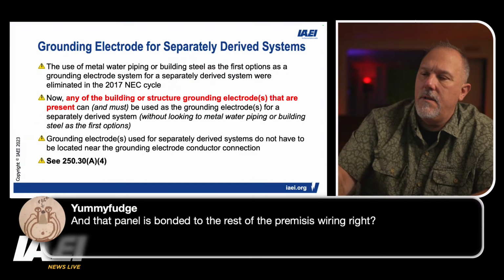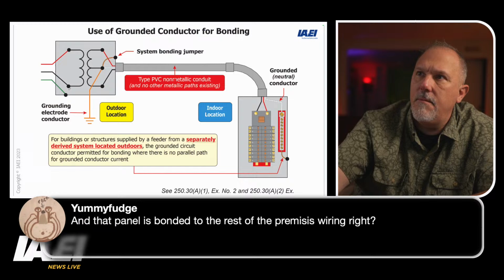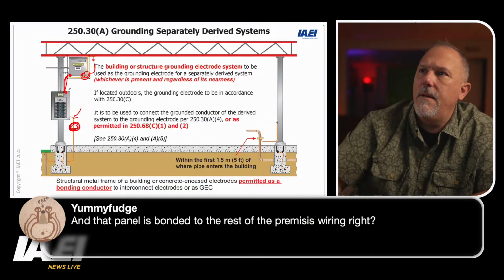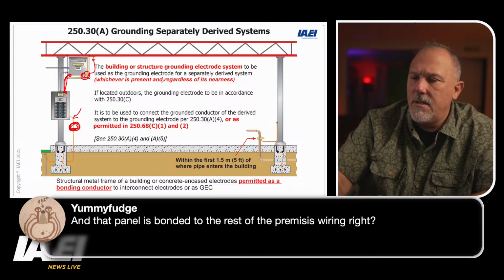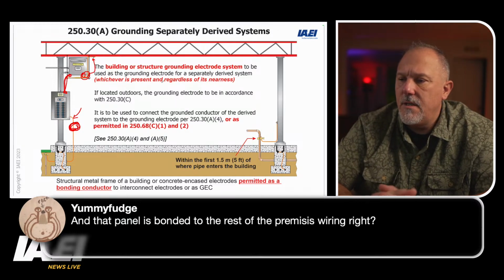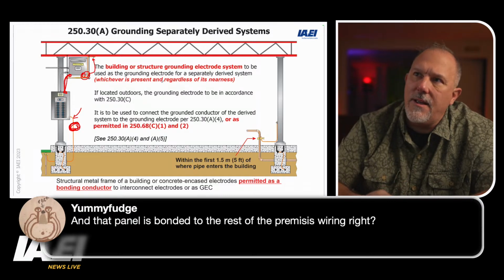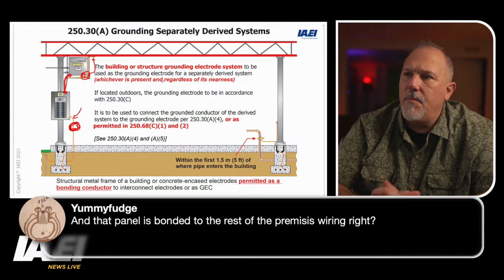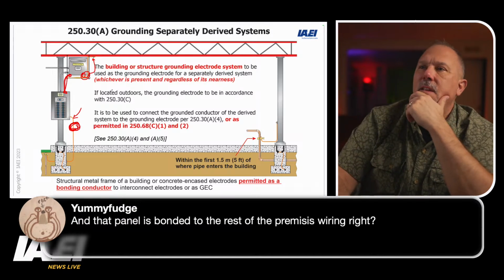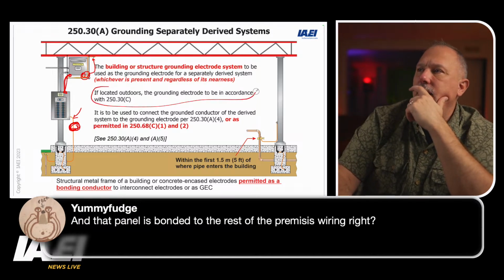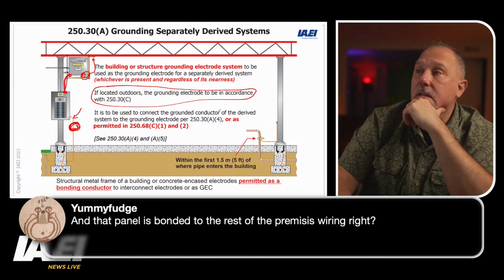Whoa! Sorry about that, I went the wrong way. And regardless of its nearness, I think they're trying to show two different concepts, one for the inside transformer and one for the outside. You're probably right, but it's not clear to me. Yeah, there it is. If located outdoors, the grounding electrode is to be in accordance with 250.30(C), and it is to be used to connect the grounded conductor of the derived system to the grounding electrode.